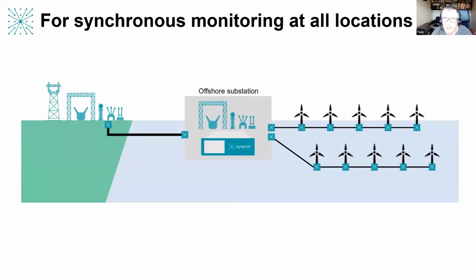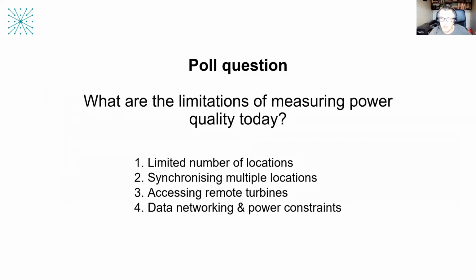Just on this slide, I think it's useful to say, as well as measuring synchronously from all the turbines, which is useful because, as you'll hear, you don't get additions and subtractions, which you would get if you measured just at the substation end, which I think is the conventional way to do it. But you can combine those with measurements on the substation, both at the 66 and 220 kV side, and also on the onshore substation. So you're getting this really big detailed picture of power quality. As we've mentioned, it's synchronous, so there's no need to take it in multiple locations and try and marry up all this data. If we can just go to the next slide, Stephen, I'll pass on to you.